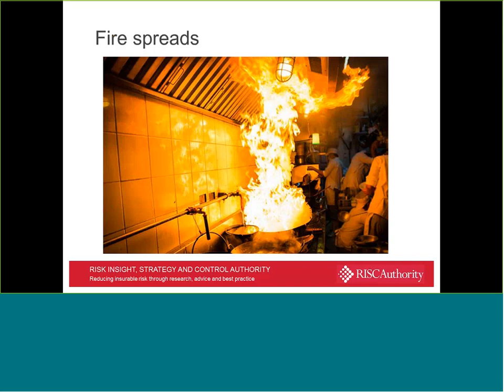Why are we concerned about extract ductwork? Well, in real terms, we recognise that the hood is often some distance above the cooking surface, but as the photograph on the slide shows, it's not uncommon for flames to spread quite some height from the flammable vapours that are given off through the cooking process and the oils and the greases that are used in the process. Similarly, you may be cooking burgers, and if they all spit at the same time, you still may have a flame that reaches up beyond the suppression system maybe and into the ductwork and the filters themselves.